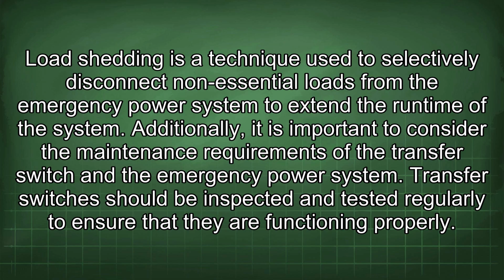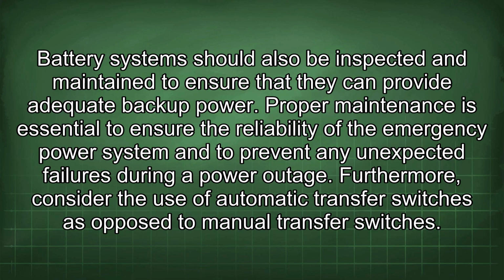Additionally, it is important to consider the maintenance requirements of the transfer switch and the emergency power system. Transfer switches should be inspected and tested regularly to ensure that they are functioning properly. Battery systems should also be inspected and maintained to ensure that they can provide adequate backup power. Proper maintenance is essential to ensure the reliability of the emergency power system and to prevent any unexpected failures during a power outage. Furthermore, consider the use of automatic transfer switches as opposed to manual transfer switches.